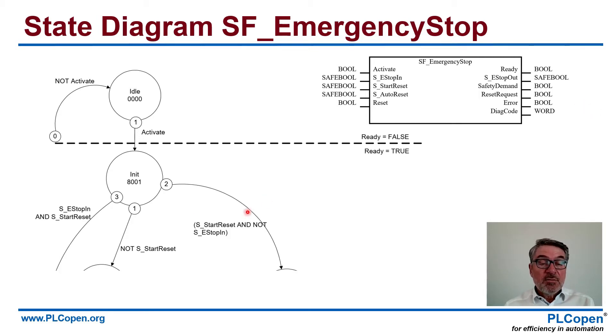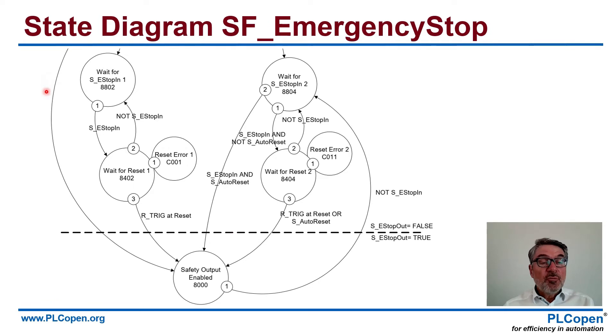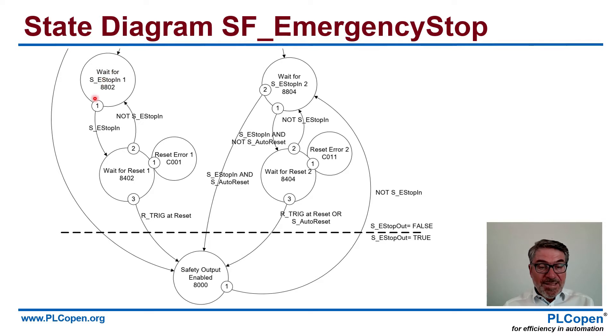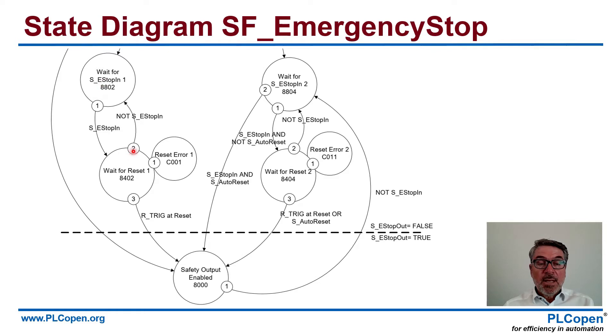There are three ways of getting out of there: one, two, and three. Not start reset, or e-stop in and start reset, start reset and not e-stop in — and they guide us through three phases. The first one goes immediately to the safe state; e-stop out is true, safety output enabled. The other one waits for the e-stop. And if e-stop in gets there, we wait for the reset, and with the R_TRIG rising edge we get to the safe output. With reset there can be a reset error. And if e-stop in is switched off, we wait again for e-stop in. So this is the one and two from priority.